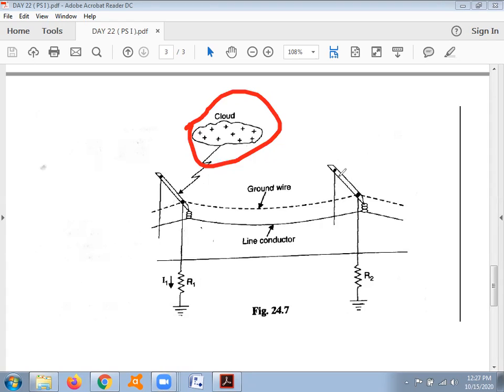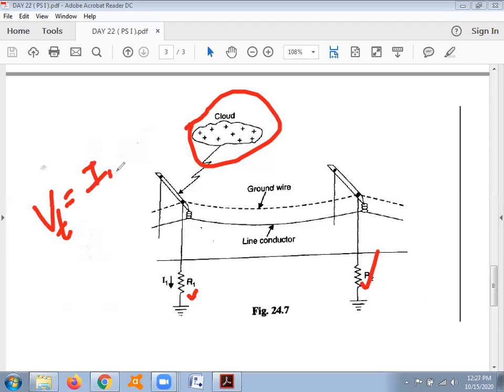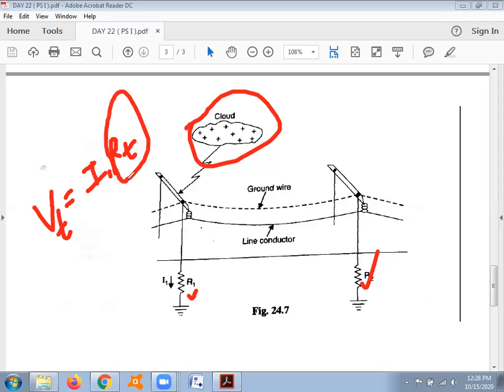The resistance of the tower to which the ground wire is connected should be kept as low as possible so that the overcurrent can easily flow to the ground. The footing resistance of the tower is of considerable importance in the case of direct lightning strokes. The formula relates the potential difference between the conductor and the tower as V = I1 × RT, where I1 is the overcurrent from the cloud discharge and RT is the total footing resistance of the tower. In order for all currents to flow to the ground, RT should be kept as low as possible.